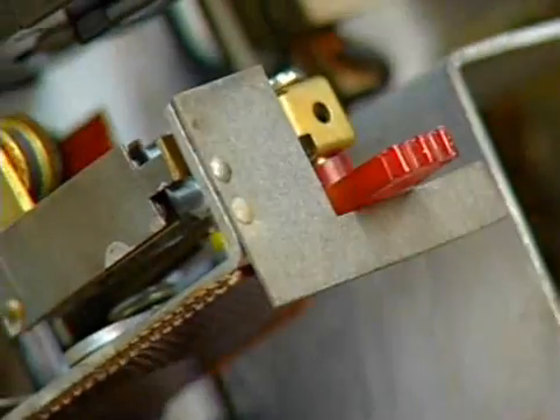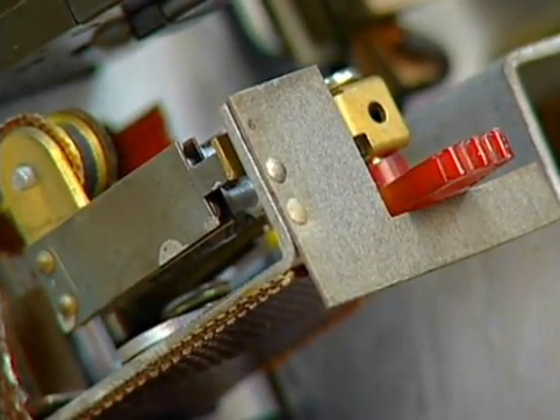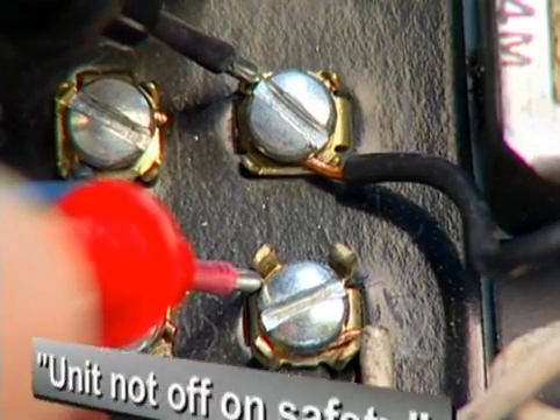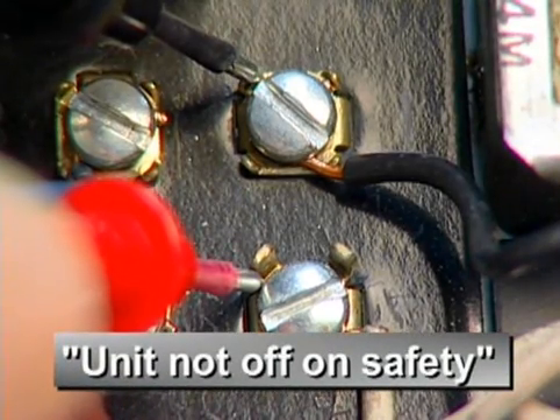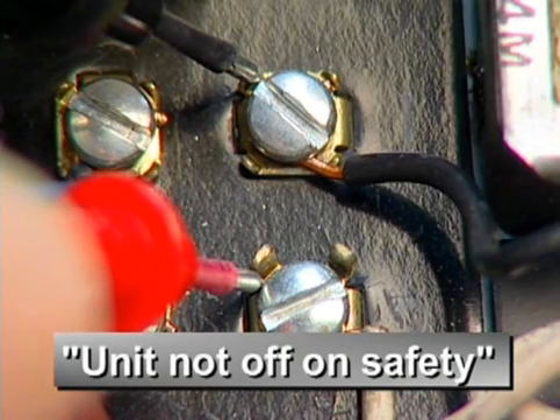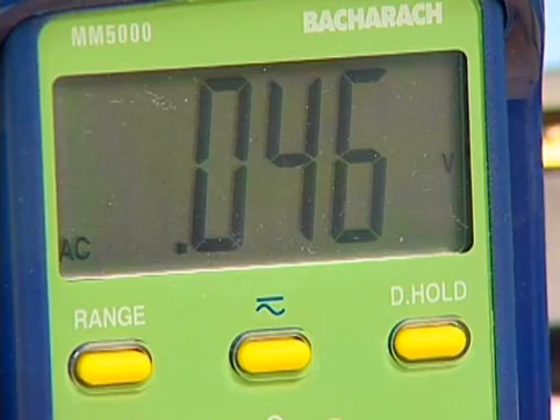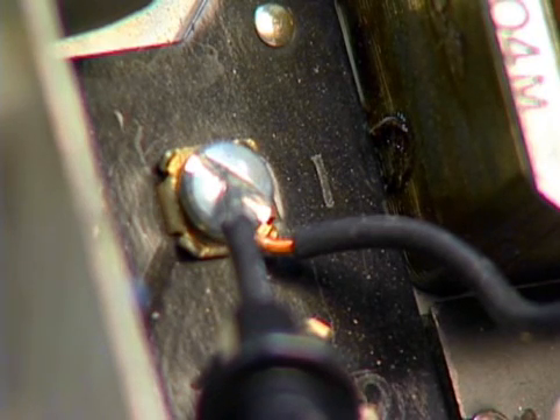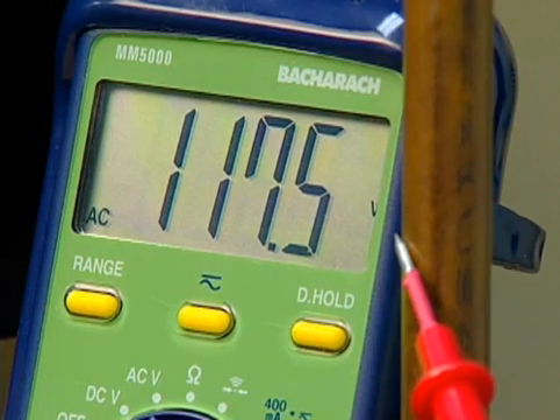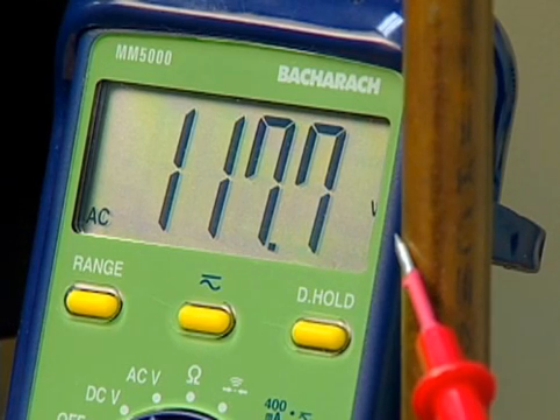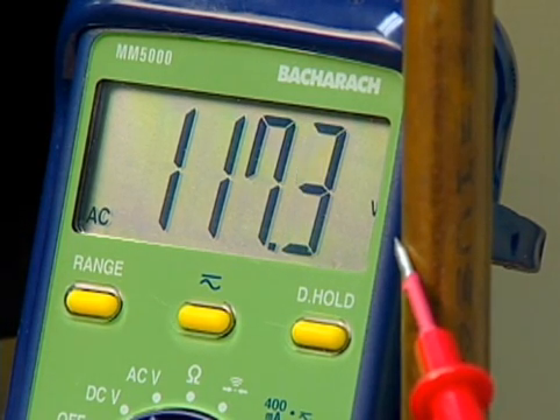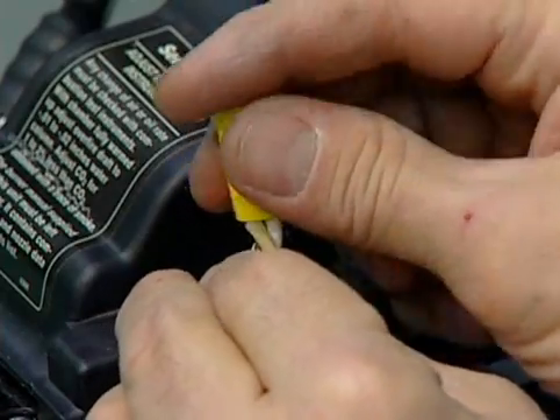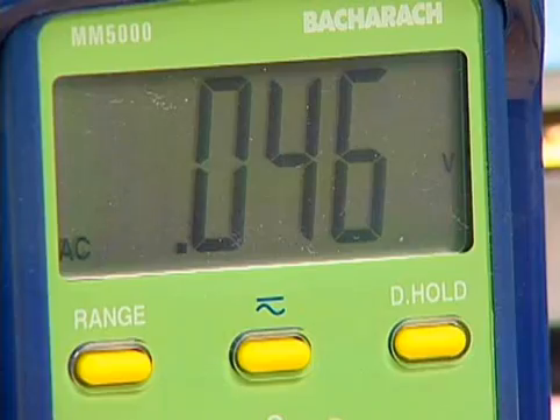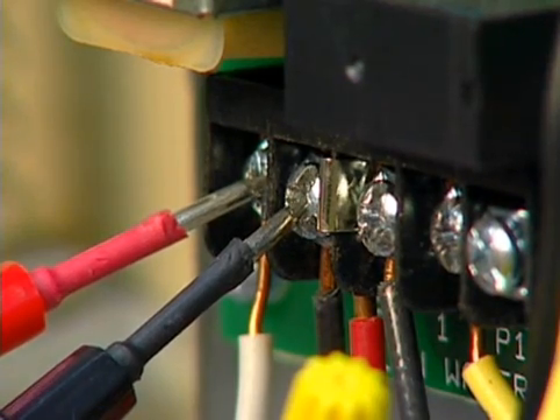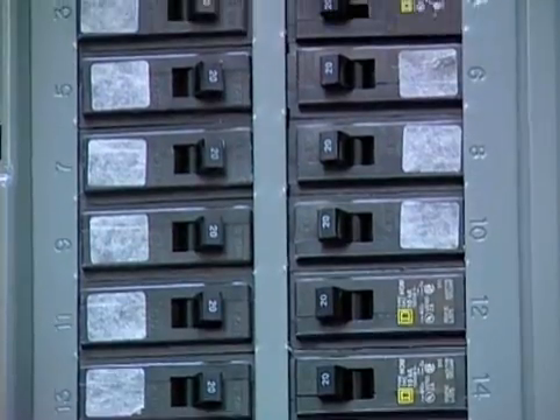Remove the cover and visually check the spring-loaded reset to see if the unit has shut off on safety. If the primary control is not off on safety, check for the proper voltage between terminals 1 and 2. If there is no reading on your meter, leave one probe of your meter on terminal 1 and touch the other probe of your meter to a copper water pipe. If you now have a reading on your meter, the trouble is in the neutral leg. Check for a broken neutral back through the system. If there's no voltage even when you touch the probe to the water pipe, check for power at the limit controls, the switch, and the fuse or circuit breaker.